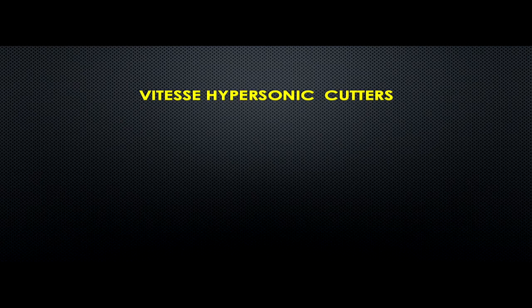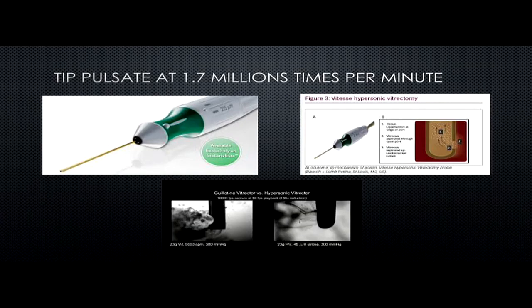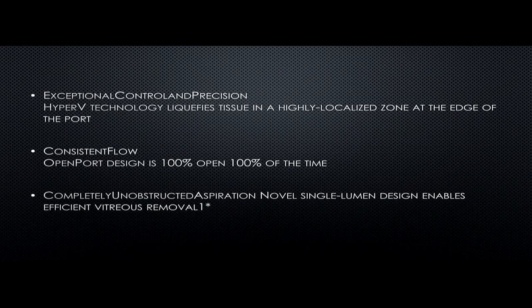The bevel tip design allows the cutting port to be close to the retina, reduces traction, and provides increased surgical efficiency. The second new cutter is not yet commercially widely available — it's only with the Bausch and Lomb Stellaris platform. This is the hypersonic cutter; the tip pulsates 1.7 million times per minute, the port remains 100% open at all times. The manufacturer claims very less traction, much higher flow, exceptionally controlled precision, consistent flow due to 100% port open time, and complete unobstructed aspiration with a novel single lumen design.